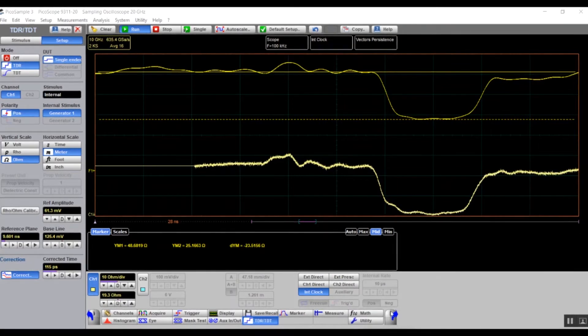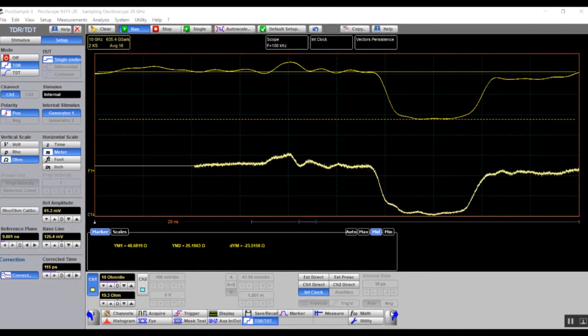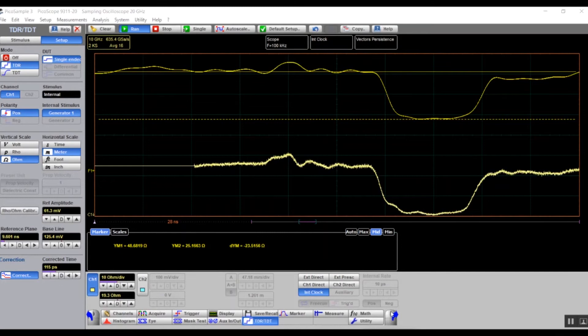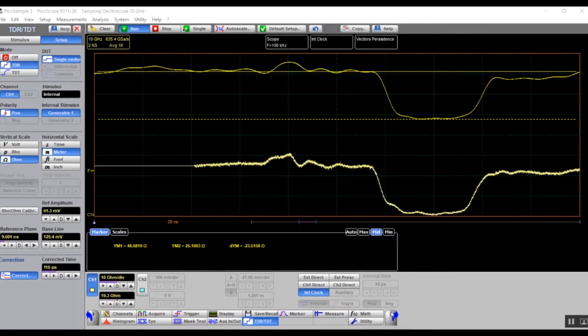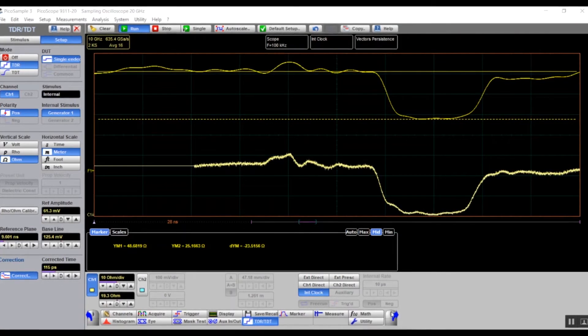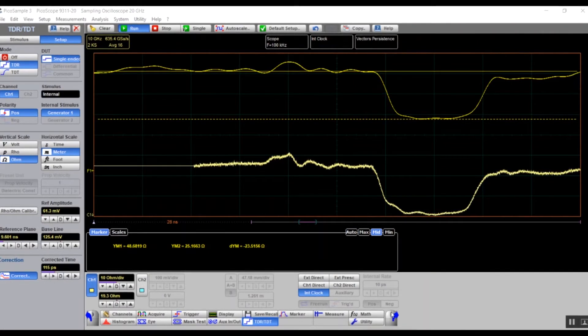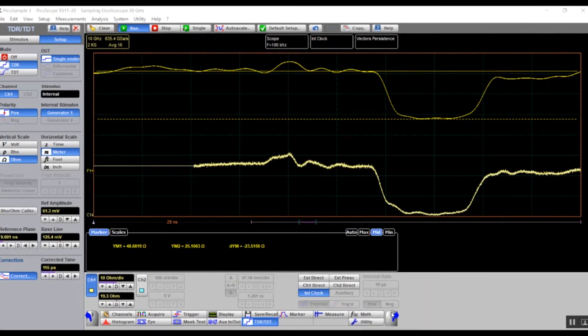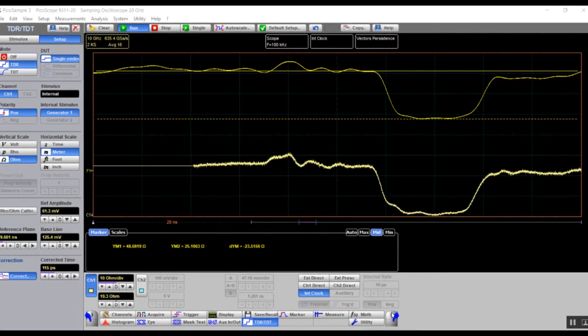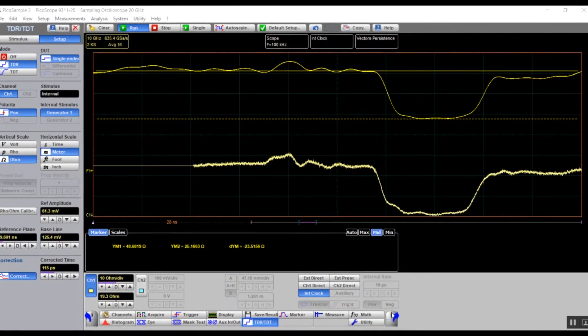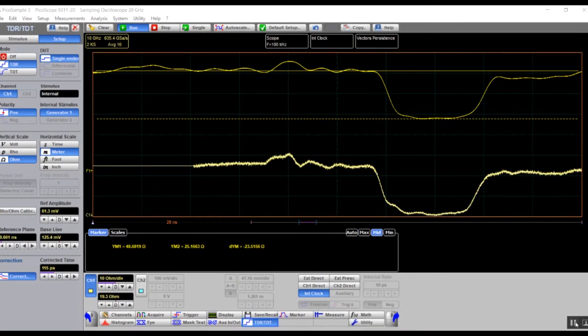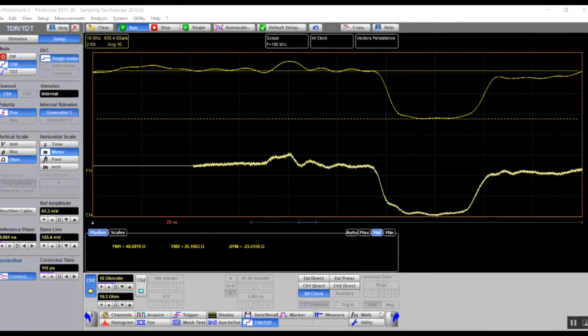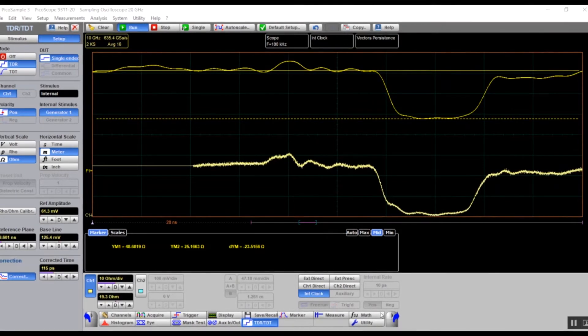We are now going to use markers to characterize our mismatched line. We can use the horizontal marker for impedance measurement and the vertical for distance measurement. You will see two traces on the screen: the dark yellow trace, the corrected trace, and the lighter trace, channel 1. We will take our measurements from the corrected waveform.